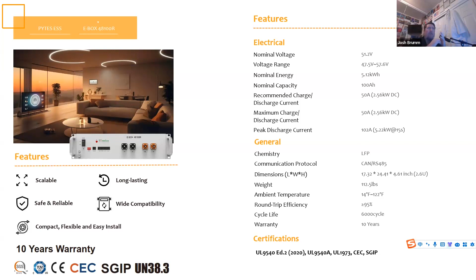Generally speaking, with lithium iron phosphate, you're looking at maybe 8,000 cycles or so if you have that battery sized at 80% depth. So 90% is a strong capability. But if you get strategic in how you're sizing it, you can increase the life cycles quite a bit just by oversizing your battery 20% larger than your daily need, or at 80% depth of discharge. Am I wrong, or is that correct?